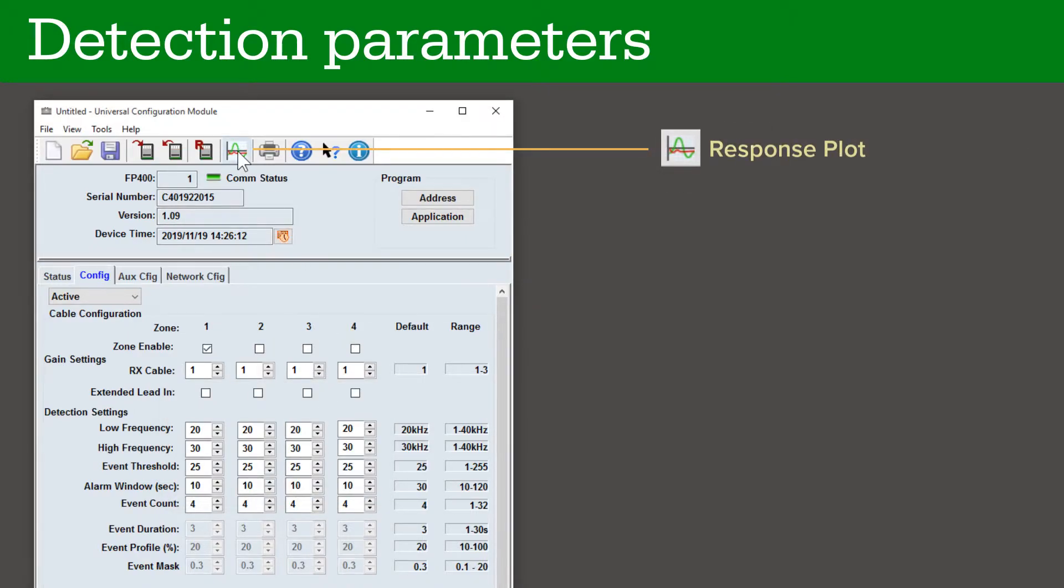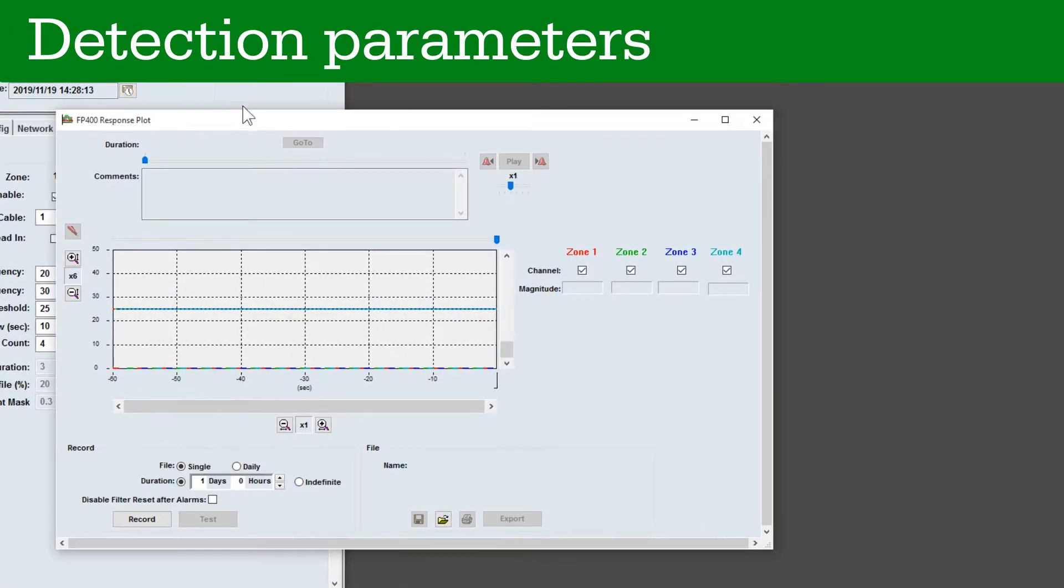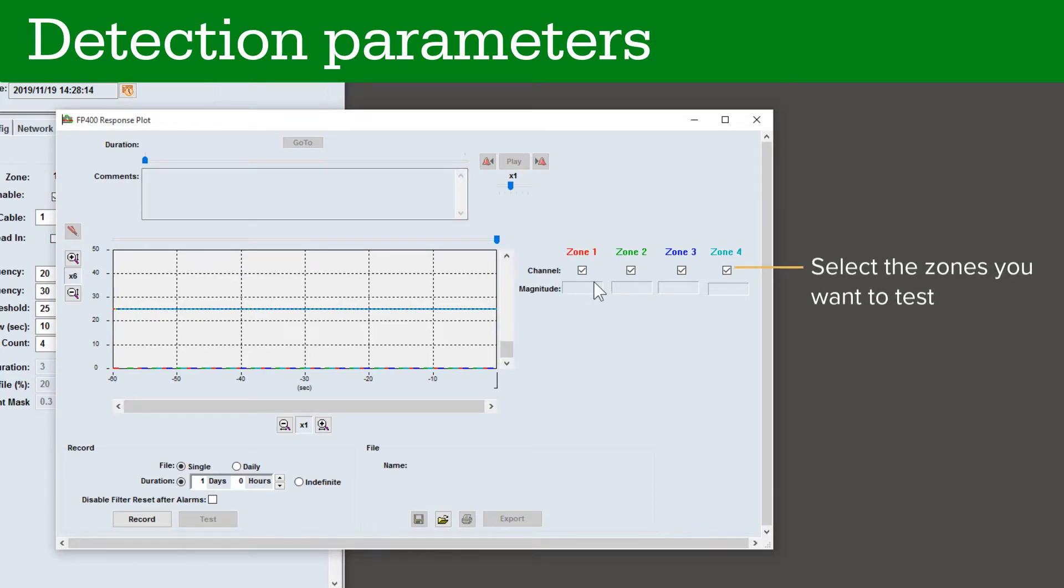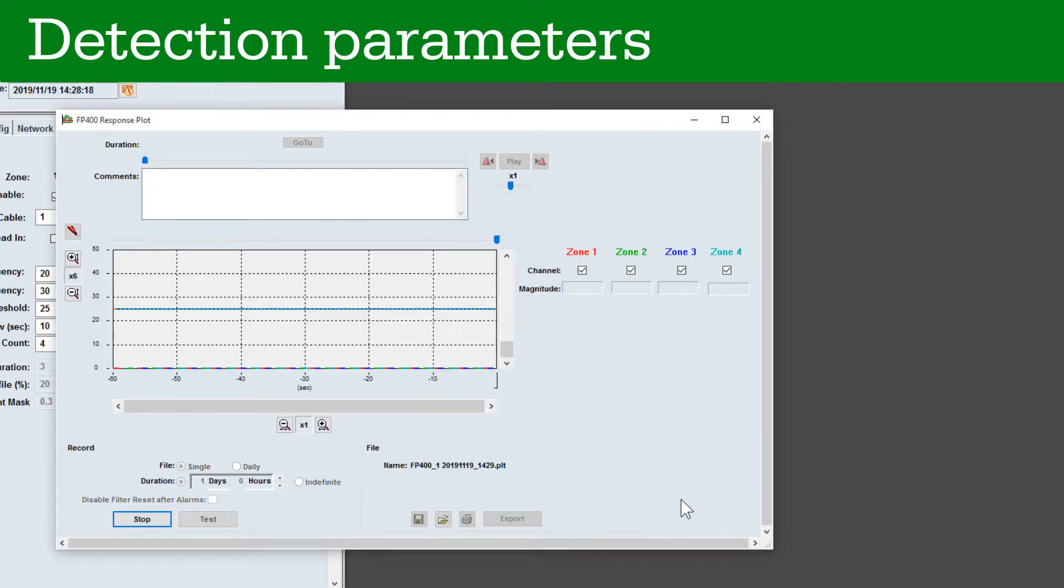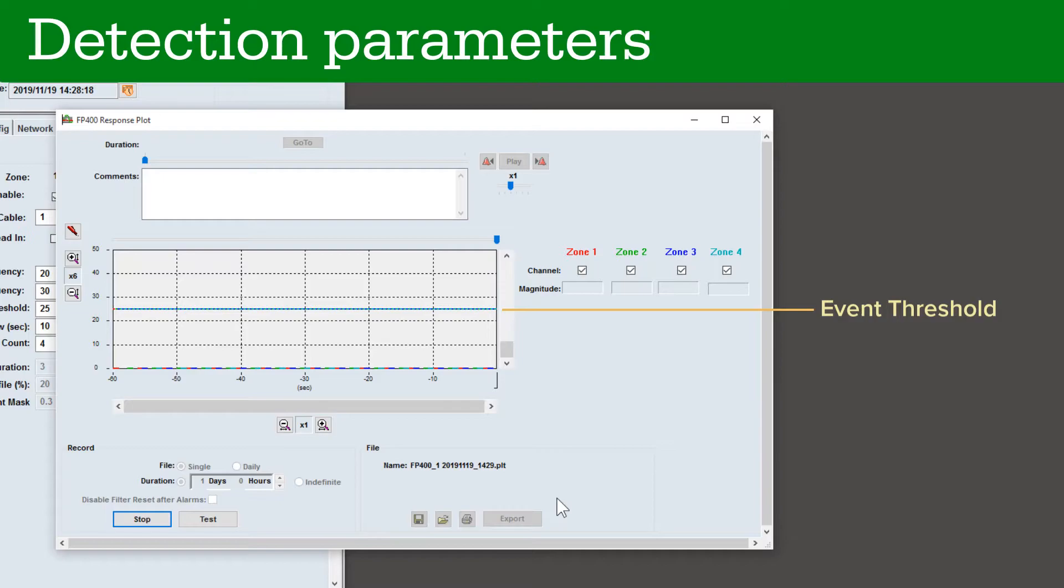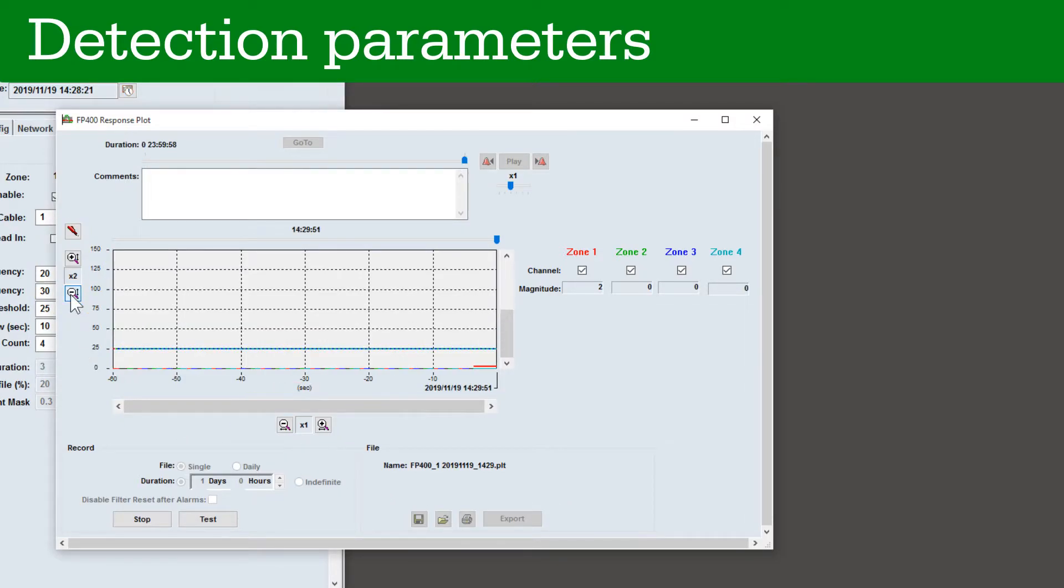To test the active detection settings, click Response Plot. Select the zones you want to test and click Record. Select a location for the response data and click Save. The blue line is the event threshold. A disturbance must go above this line in order for it to be accounted as an event that contributes to an alarm being generated. Click the Zoom buttons to zoom the plot in or out.